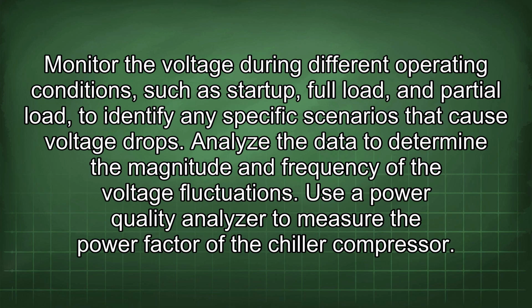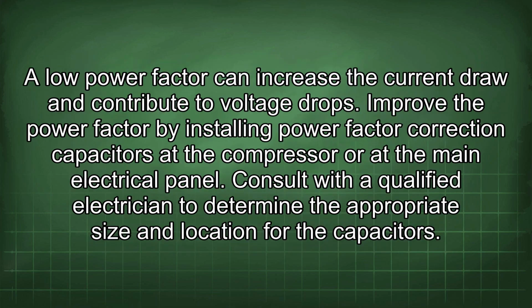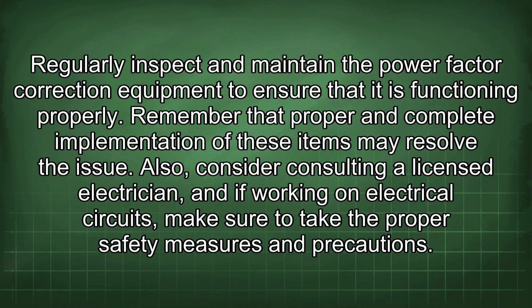Use a power quality analyzer to measure the power factor of the chiller compressor. A low power factor can increase the current draw and contribute to voltage drops. Improve the power factor by installing power factor correction capacitors at the compressor or at the main electrical panel. Consult with a qualified electrician to determine the appropriate size and location for the capacitors. Regularly inspect and maintain the power factor correction equipment to ensure that it is functioning properly.